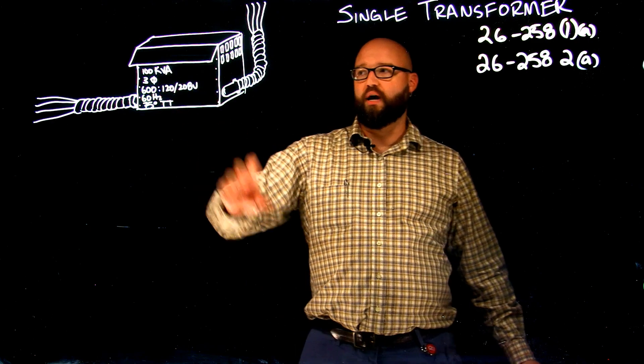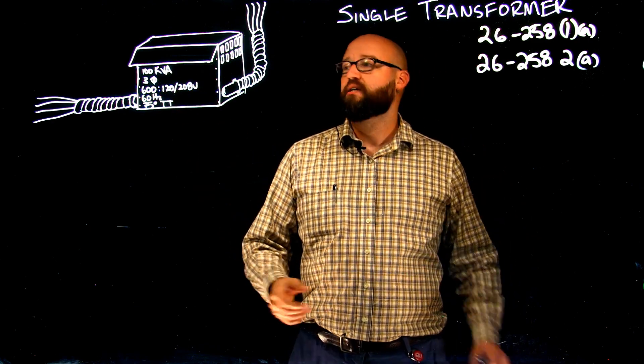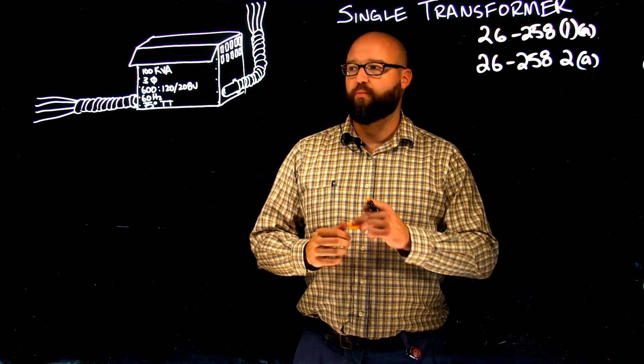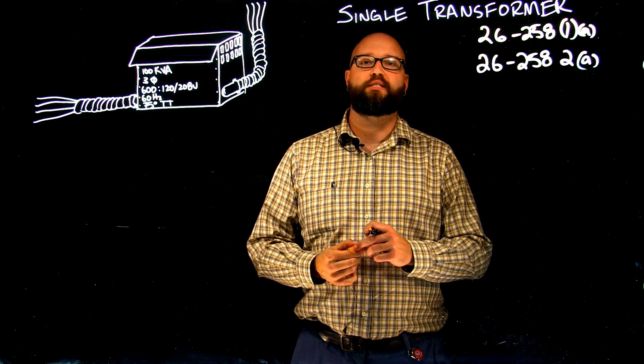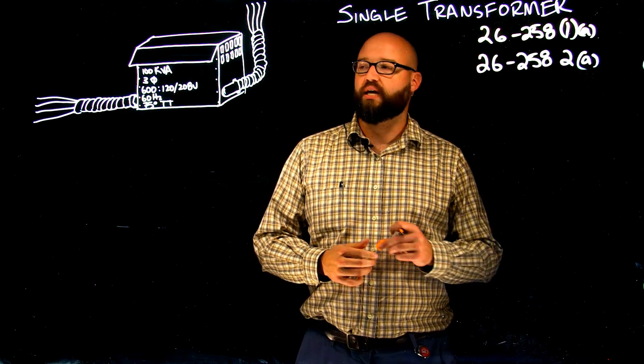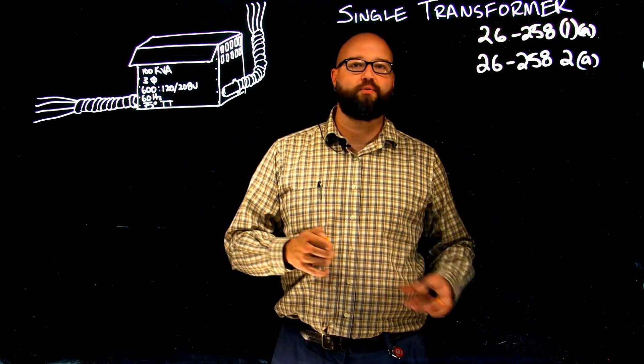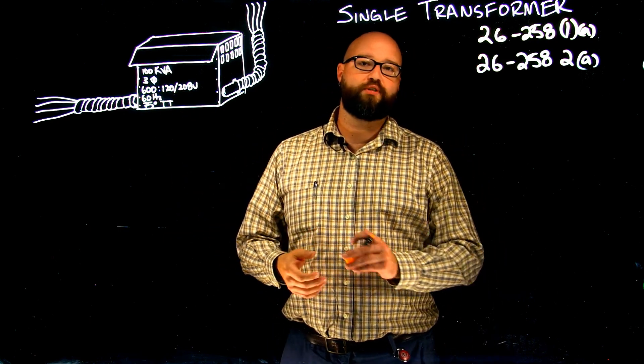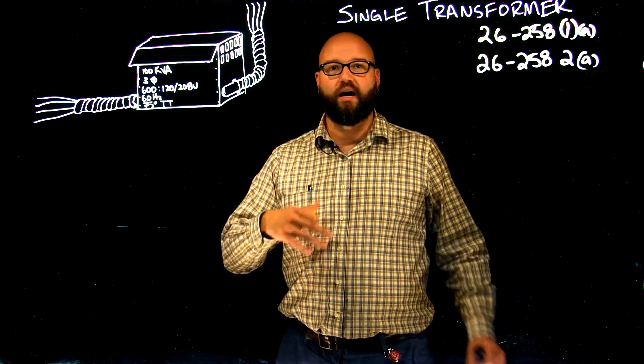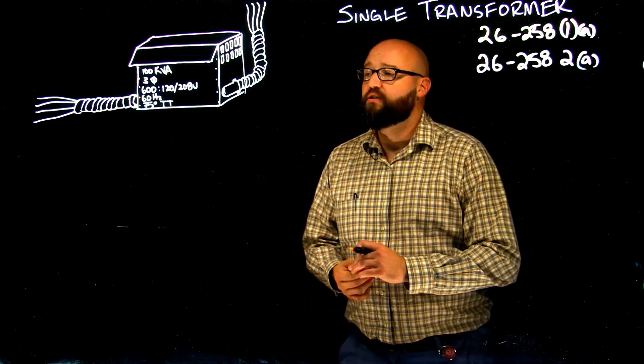What we have here, I have a 100 kVA transformer, three-phase transformer, 600 step down to 120/208 secondary voltage, 60 hertz, and we've got a 75 degree termination temperature, so we need to keep in mind rule 4-006 when selecting conductors from table 2. So, we'll get started.